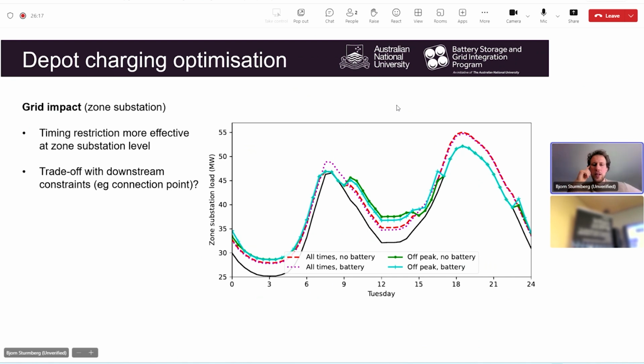It does a bit during the morning peak, but the bigger difference in those four scenarios is that the increase in peak demand during the middle of the day can comfortably be accommodated by the zone substation, because the load is generally low there throughout the middle of the day. Whereas the impact that charging during the afternoon evening peak has is really significant, because it either adds a couple, like 3 megawatts of demand onto the zone substation that's already at its limit, or it doesn't add any demand at that period.